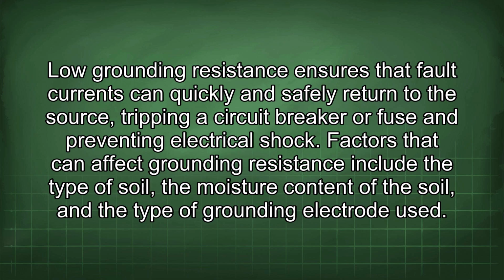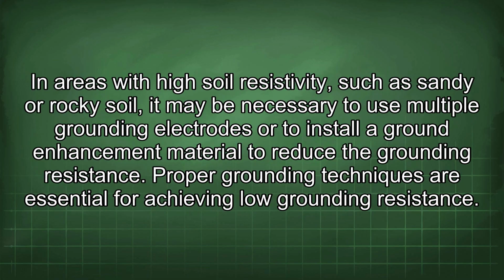Factors that can affect grounding resistance include the type of soil, the moisture content of the soil, and the type of grounding electrode used. In areas with high soil resistivity, such as sandy or rocky soil, it may be necessary to use multiple grounding electrodes or to install a ground enhancement material to reduce the grounding resistance.